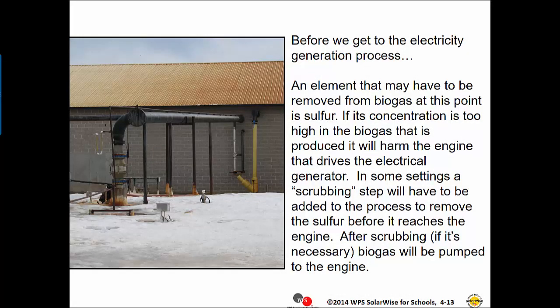Before we get to the electricity generation process, an element that may have to be removed from biogas at this point is sulfur. If its concentration is too high in the biogas that is produced, it will harm the engine that drives the electrical generator. In some settings, a scrubbing step will have to be added to the process to remove the sulfur before it reaches the engine. After scrubbing, if it is necessary, biogas will be pumped to the engine.